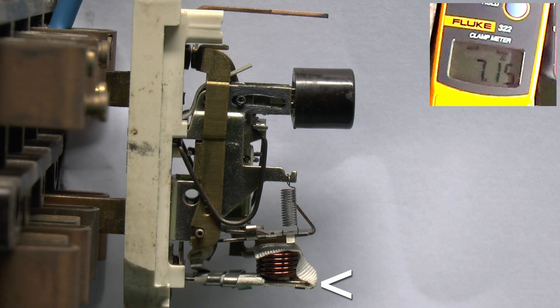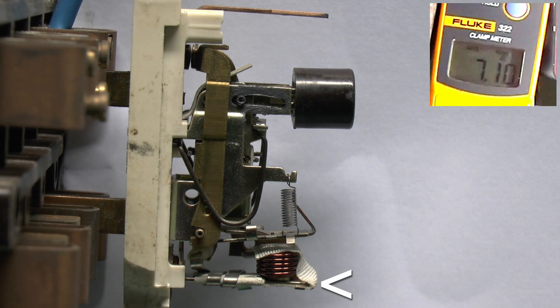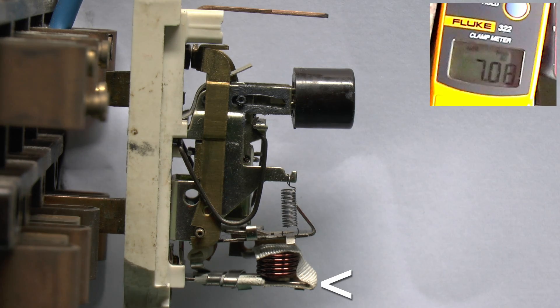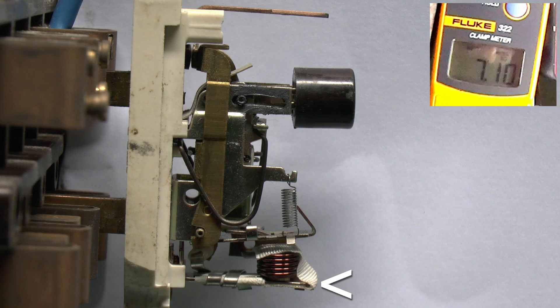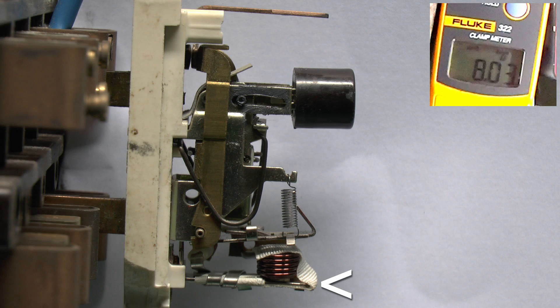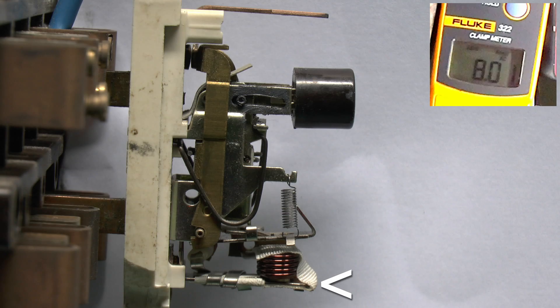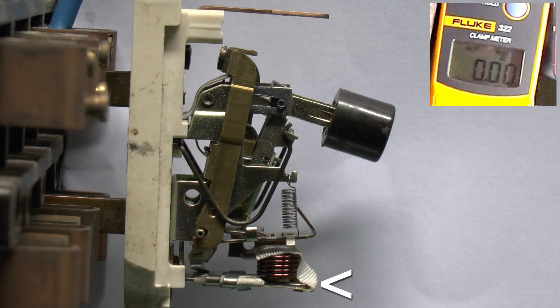Now I think we'll just turn up to around 7. And then we'll just see if the strip does actually bend downwards. So you can just about see it slowly moving down there. That's right, 8A there. And again that's enough to trip the device.